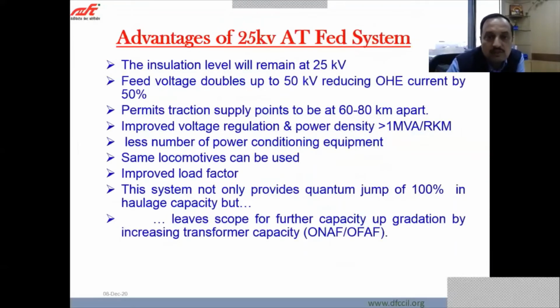If we summarize these advantages, our insulation level for equipment is at 25 kV, whereas for the voltage drop, the feed is doubled at 50 kV. Therefore, it reduces the current by almost 50%, which leads to a distance between traction points of 60 to 80 km, whereas in the case of IR it is 30 to 40 km only. There is improved voltage regulation, and power density is more than 1 MVA per RKM. There is also a lesser number of power conditioning equipment. The same locomotives that run on the Indian Railways can be used. There is not much difference.